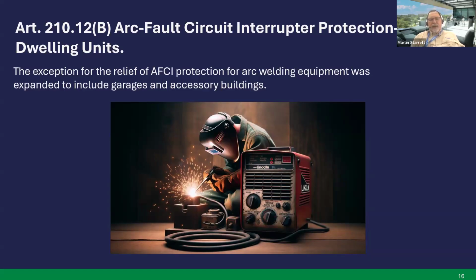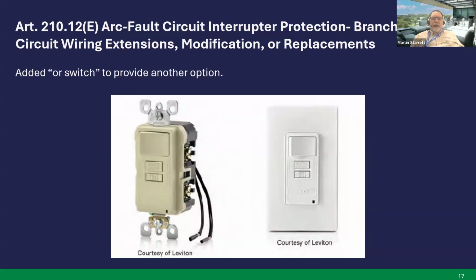FYI, National Electrical Safety Month: arc fault circuit interrupters are another electrical safety device that helps protect the home against electrical fires. Next slide. Also in Article 210.12(E), where you have branch circuit wiring extensions, modifications, or replacement, they added the words "or switch." This provides another option when you're doing extensions or modifications. They make an arc fault type switch now, so where we've had to use devices or receptacles before, now in 2026 you could actually use one of these switches.